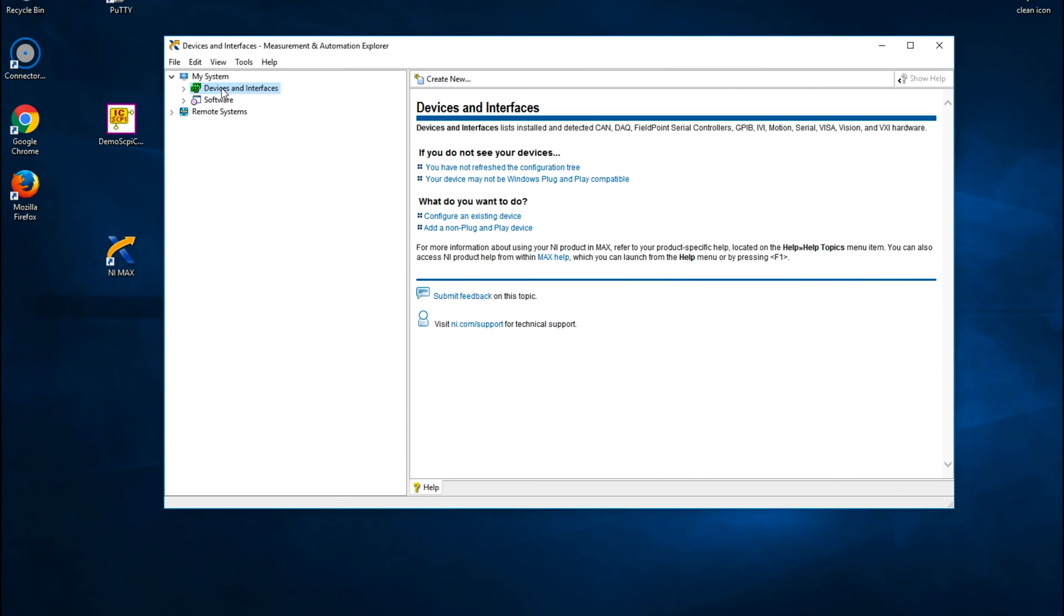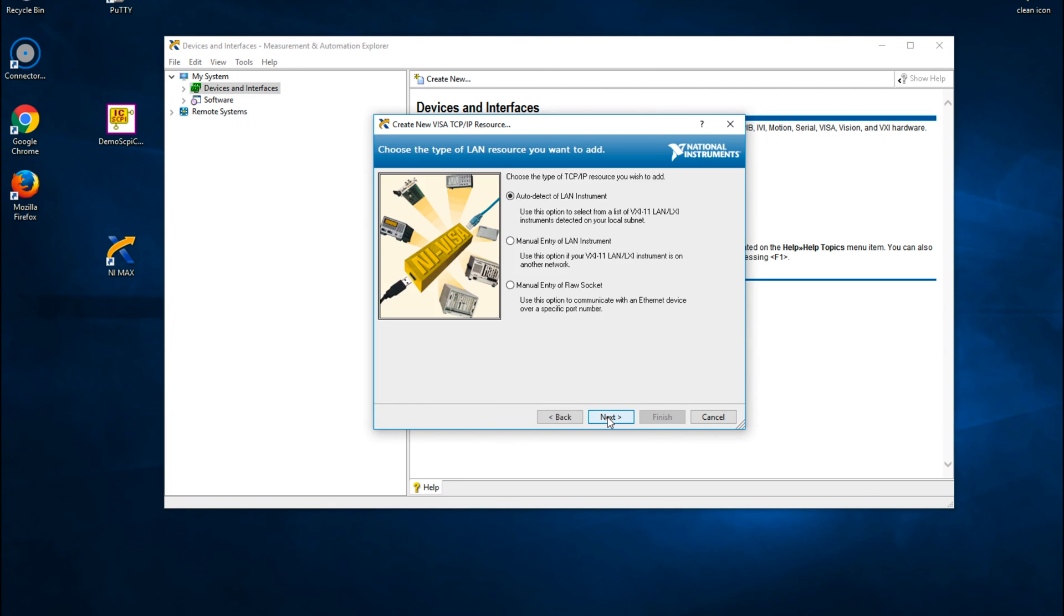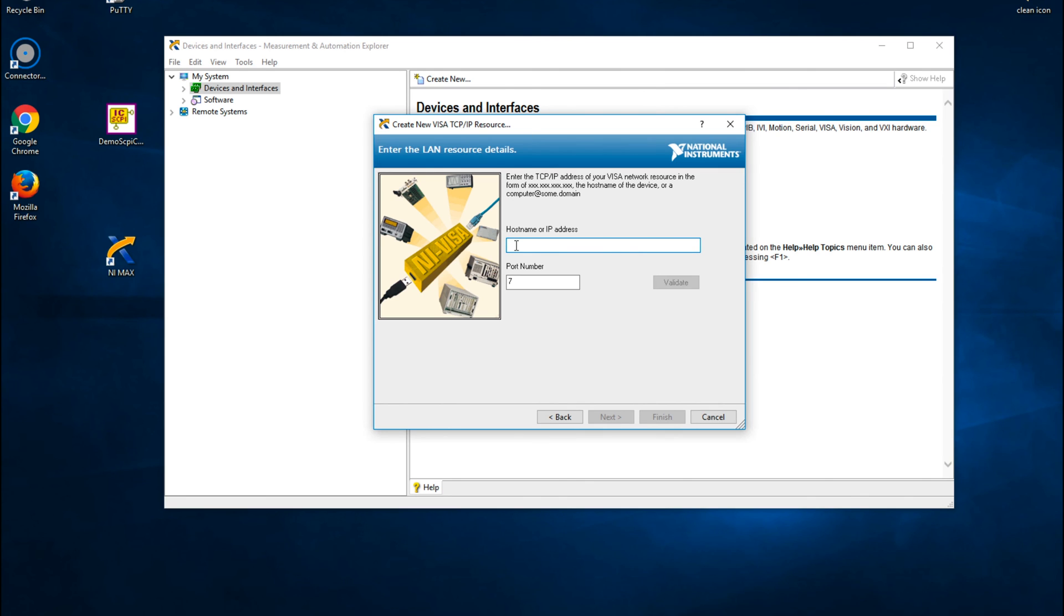Right-click on Devices and Interface item and select Create New. Select VISA TCP IP Resource and press Next. Select Manual Entry of Raw Socket Item and press Next. Enter the workstation name or IP address, then enter the port number, which in our case is 5025, and press Next.